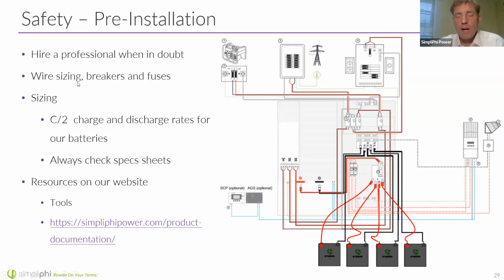Proper sizing of breakers and fuses is very important. Typically, breakers don't respond immediately at the amperage they're rated for—a 100 amp breaker might not trip until 120 amps. So don't rely on breakers and fuses as your only safety measure; make sure you size your system properly.